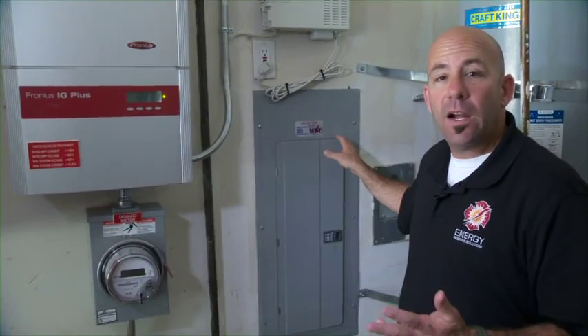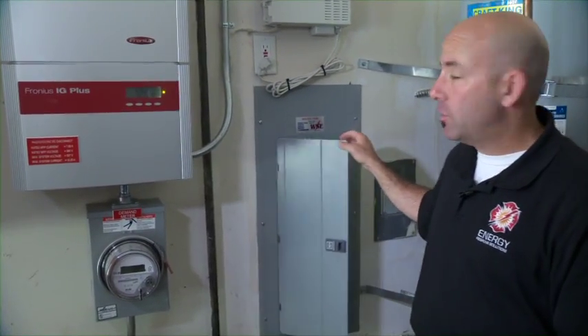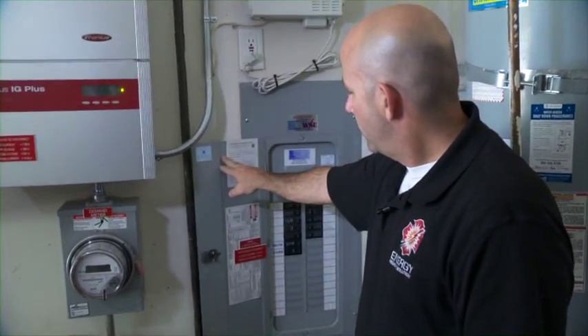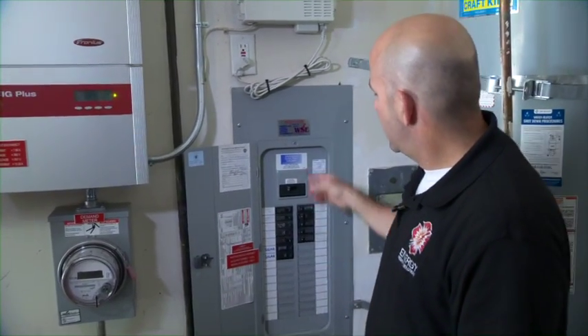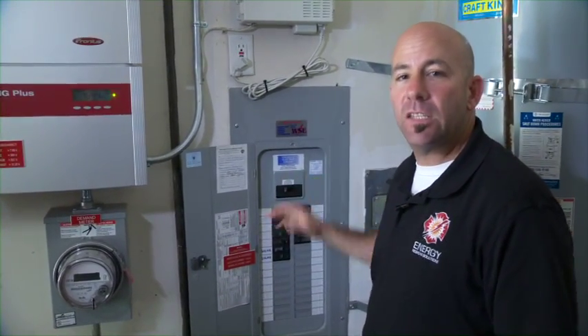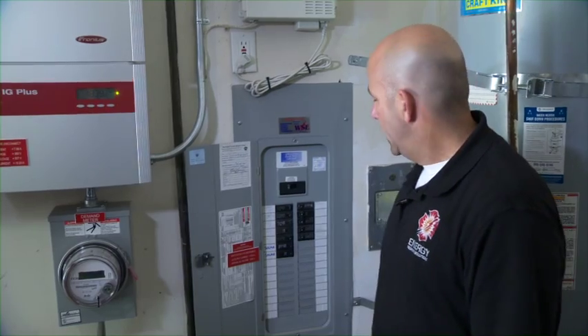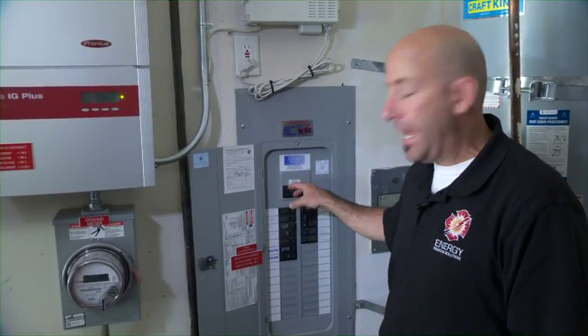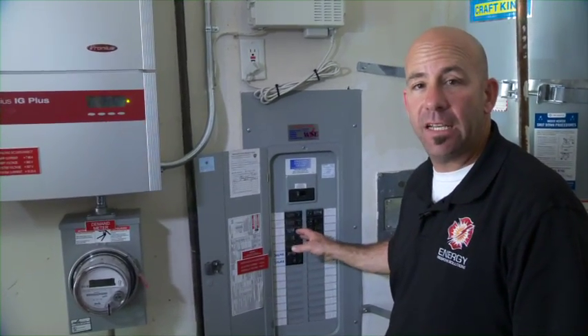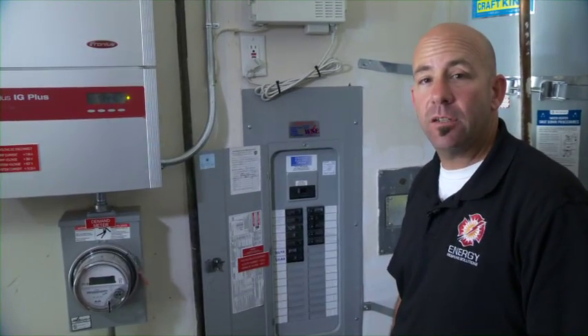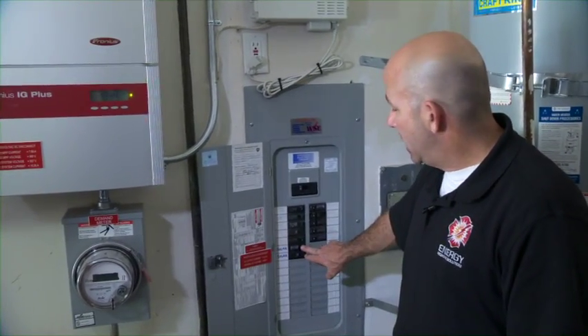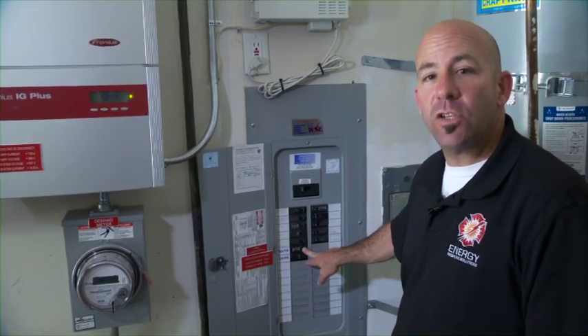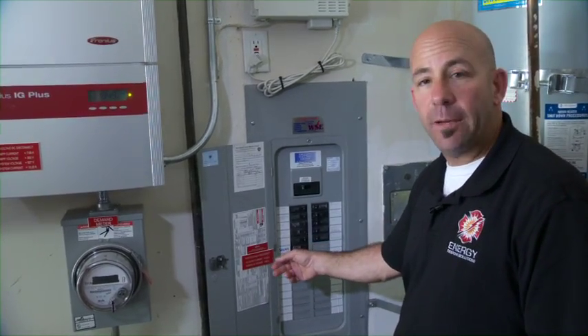Structure fire, any other fire, we're just going to go secure the utilities at the main electrical panel. What we see here is the main breaker. We shut this off, it shuts off all the power for the house. Best practice is to try and hit the main instead of all the breakers individually, so you can maintain a fire investigation scene. Here's the breaker that controls the inverter. If you just want to turn off the PV system, this breaker will do that.